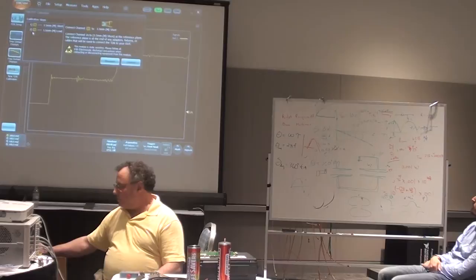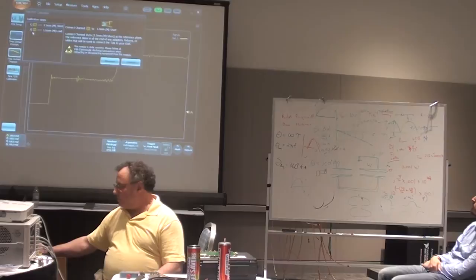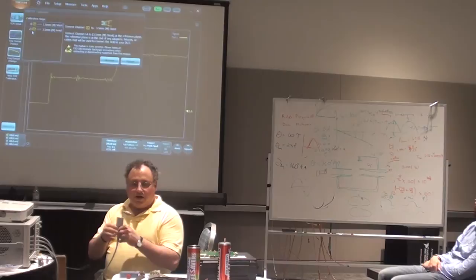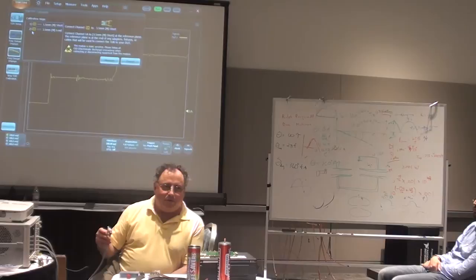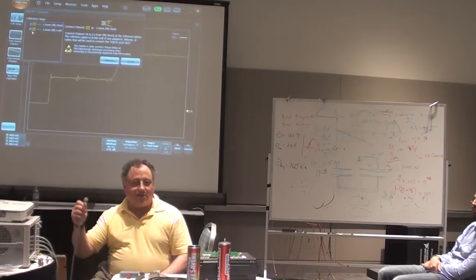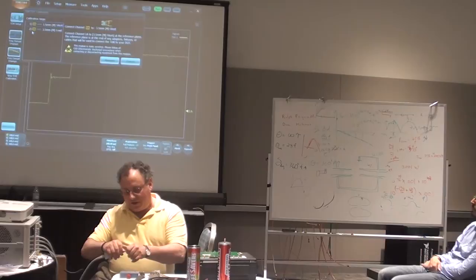And here it tells you what you want to do. It says you want to put a short circuit, press measure, and then you want to do an open circuit. The interesting thing is now when it comes to this piece right here, the connectors that are on this are nothing we have here. They're precision APC 2.4 or 2.9 millimeter. And the box in here gives us special adapters to go to SMA. So that has to happen.